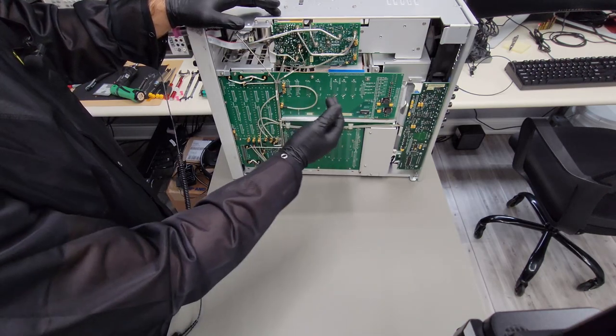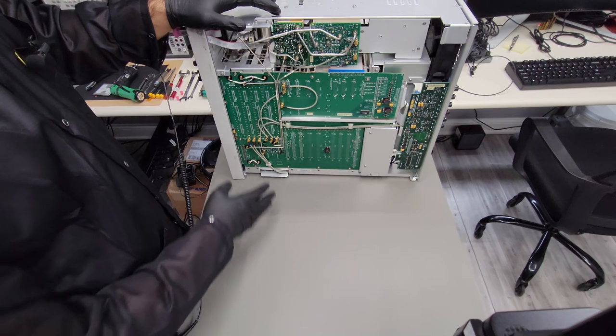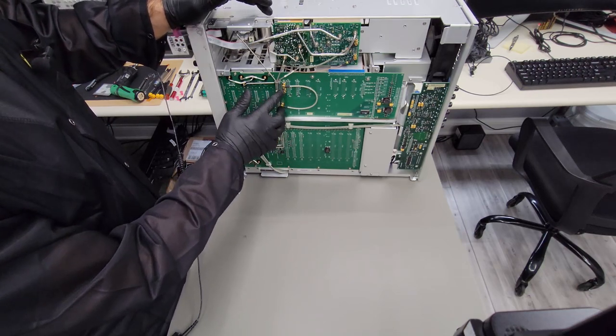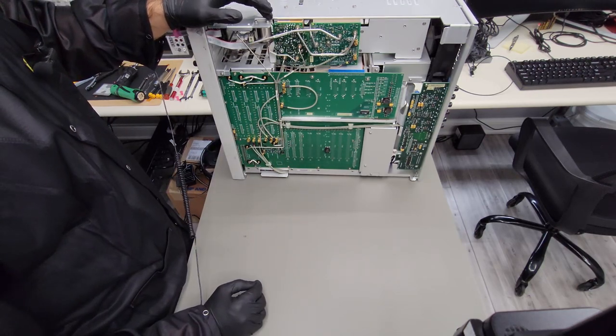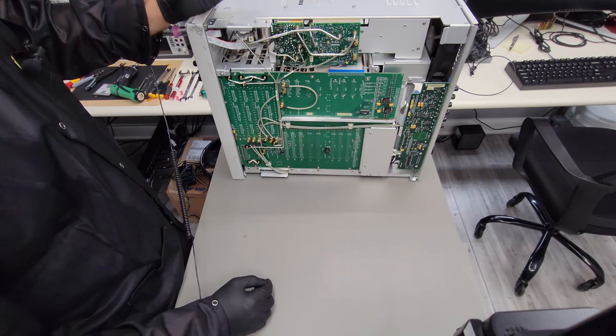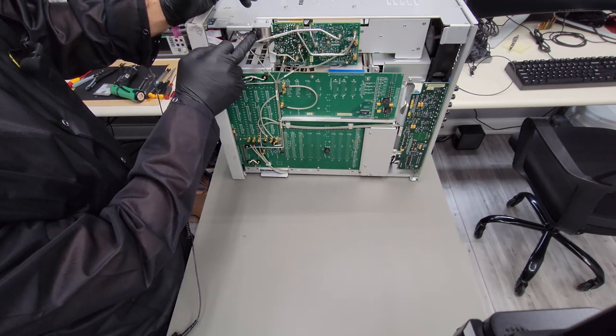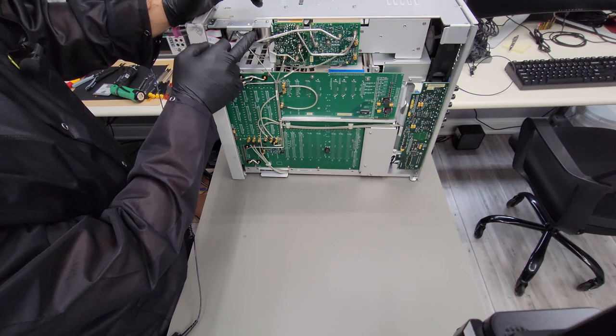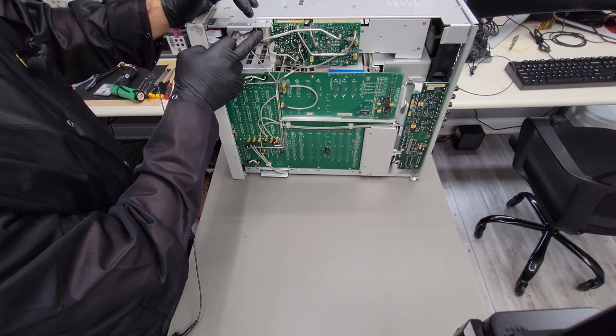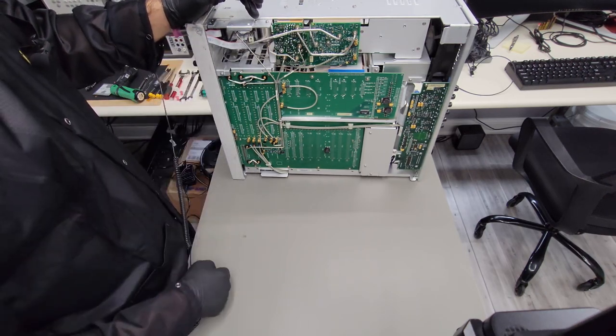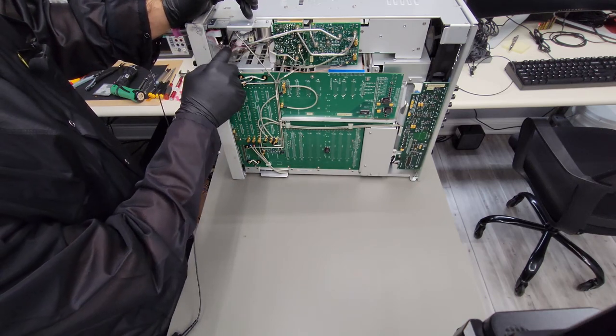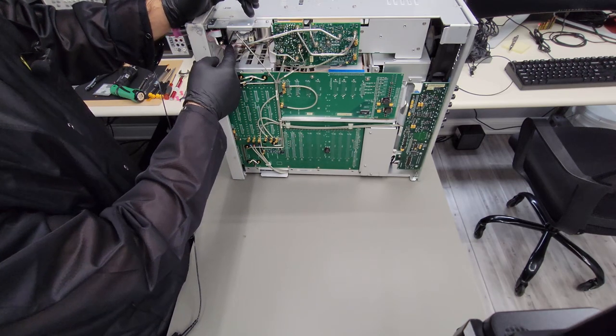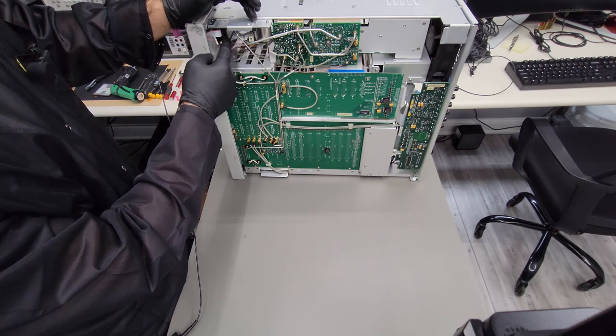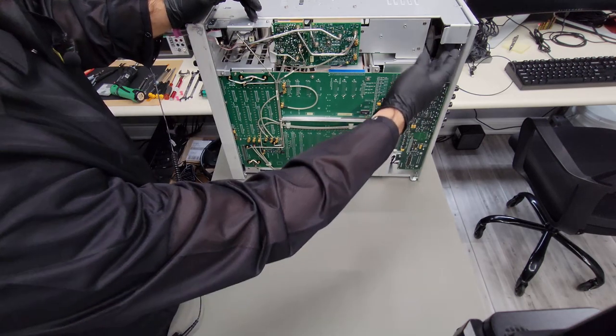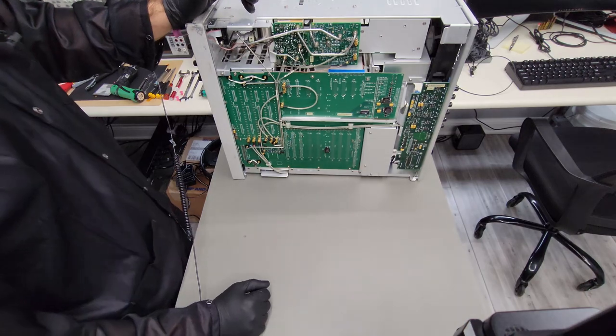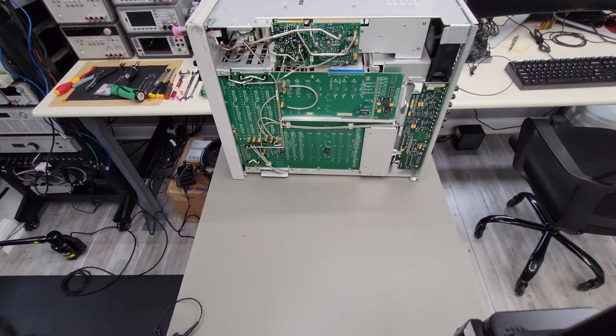So these are where all the cards attach, and then you have various coax cables for different RF signals traveling between the boards. And up here, this is the YIG-tuned oscillator itself. So that's the fundamental signal source for the RF output. And this unit has a step attenuator option here. So you can see that. And yeah, fan, rear panel board, and that's really all there is to it.